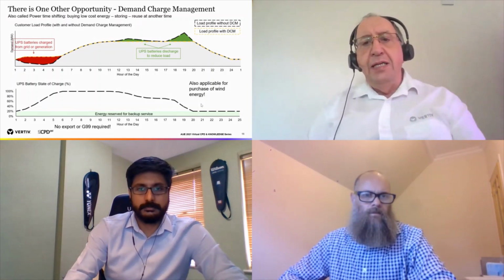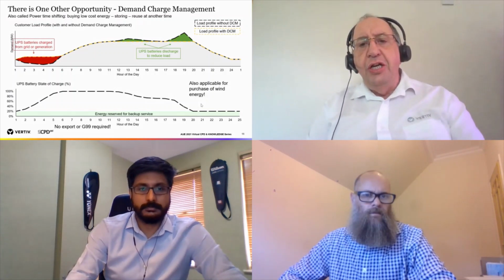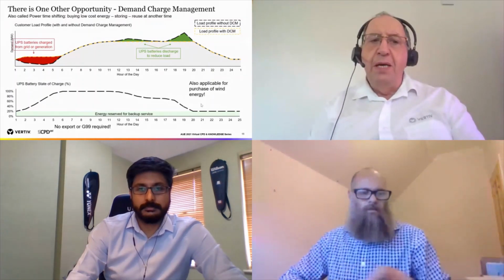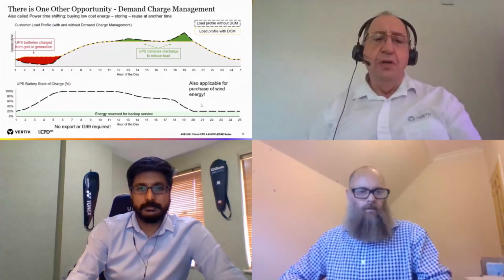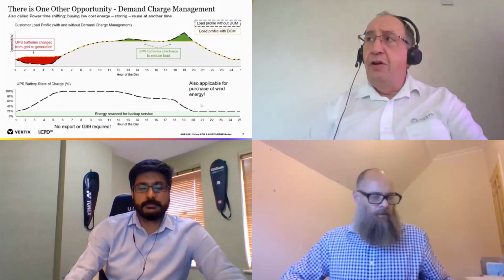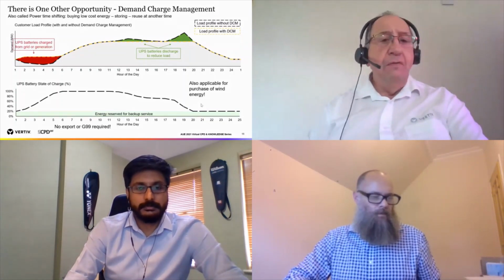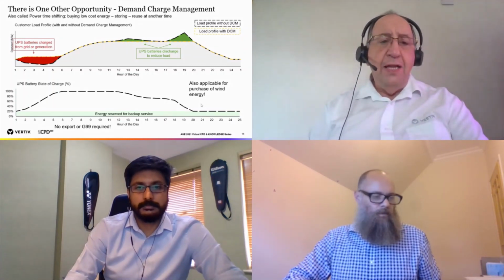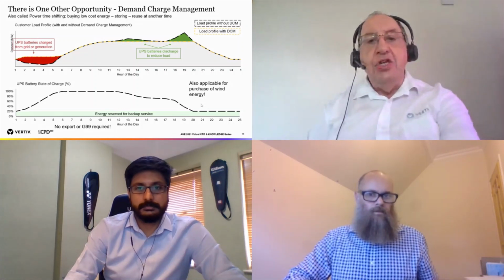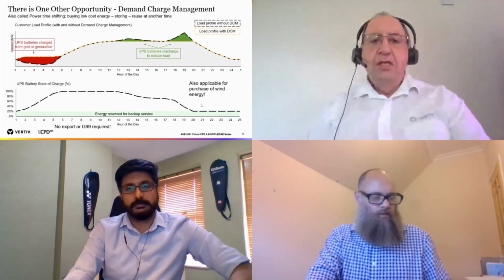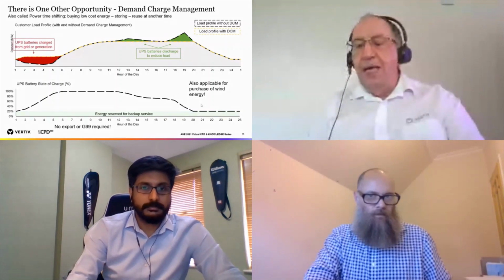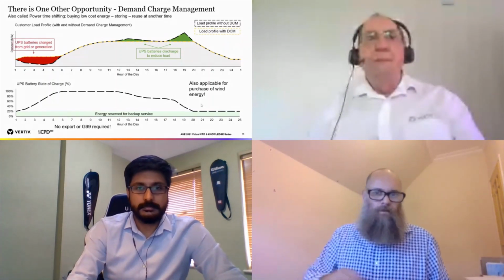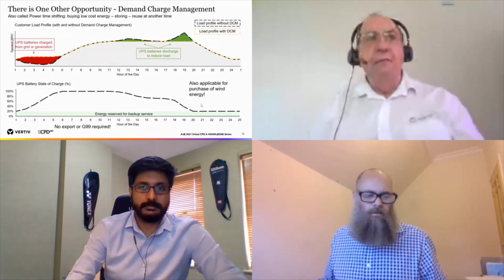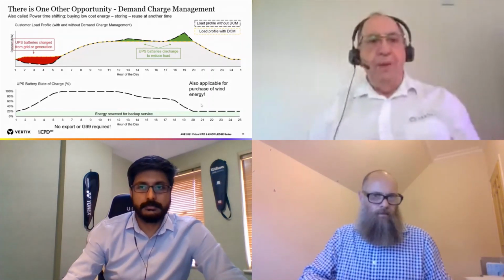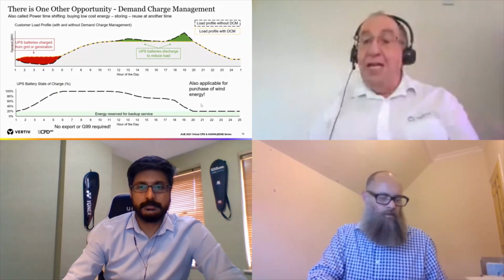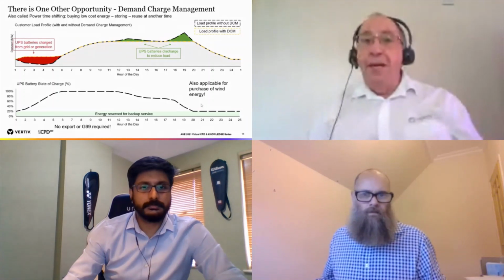The other thing that is happening is that we've got high energy costs happening at different times of the day in different parts of the country. And yet again, sorry to quote Octopus, but you can buy energy overnight from Octopus at 5p, and I understand EDF are 4p overnight. Store it in a battery, that's the red area on that diagram, and then release that energy at the peak periods during the day. So this basically means that we're using the UPS to cut off the load and to run on batteries until the batteries go down to a predetermined point and then come back online. Obviously, without a gap, without dropping the load, without any load problems. And of course, if it's really lucrative to sell the energy in the battery, then maybe inject that back into the grid and get paid for it.